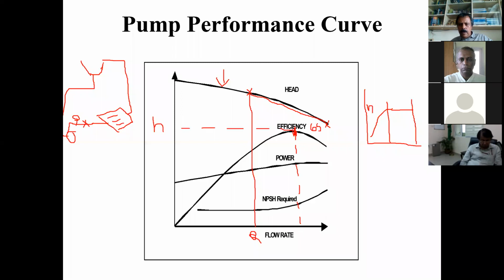And you want to now operate at a lower flow rate. What will you do? You will throttle this valve, increase the head, and lower the flow rate. Flow rate is now lowered. What happens to the efficiency? Here, if you see, the efficiency might have come down to even 40%, depending on the characteristic of the pump. So from 65% efficiency, the pump has come down to 40% efficiency, just because we have oversized the pump. The pump is rated for this flow. Now we want to operate at this flow. So there is a dramatic reduction in the efficiency where we are losing quite a considerable amount of power.